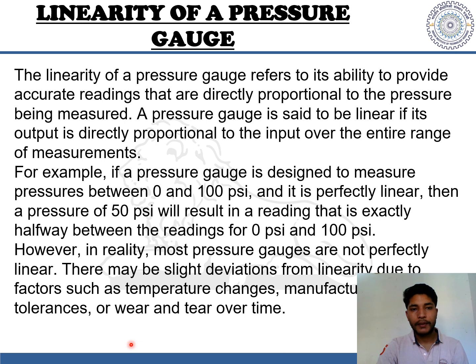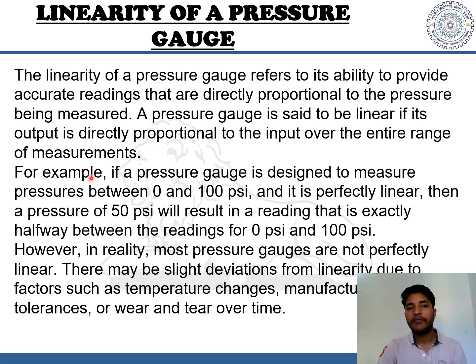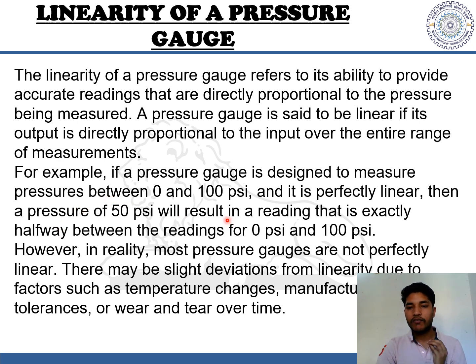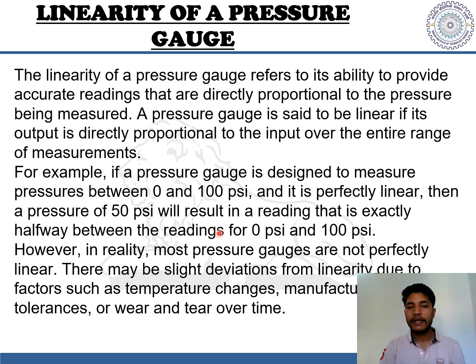Now let's look at the linearity of a pressure gauge. Linearity refers to its ability to provide accurate readings that are directly proportional to the pressure being measured. A pressure gauge is said to be linear if its output is directly proportional to the input over the entire range of measurements. For example, if a gauge is designed to measure pressures between 0 and 100 psi and is perfectly linear, a pressure of 50 psi will result in a reading exactly halfway between 0 and 100 psi.